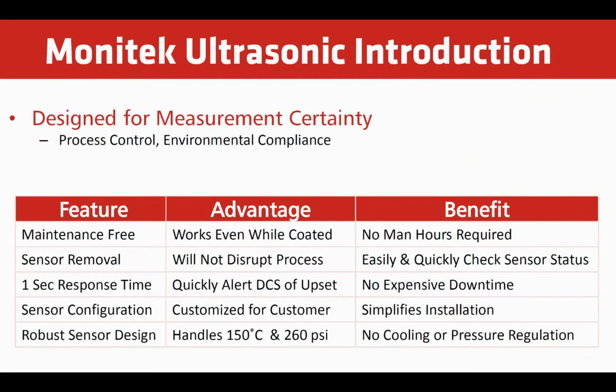It really truly is a maintenance-free analyzer. Unlike an optical device where the windows can get dirty or the lamps can burn out, this does not have those issues. It will work even if the sensor tip is coated with some particulates. So obviously no one has to go out there and do any maintenance. Sensor removal, we can do this. It is installed through a sample gland fitting and ball valve with safety chains, so you can hot tap remove it or insert it.